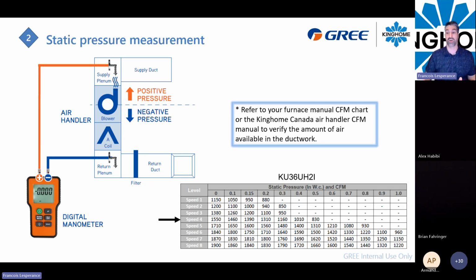If you have more than 400 CFM, the thing is, the condensate water can be blown out of the coil, so you can have some water leak if you are over 400 CFM. Also the performance will be reduced, as you will not have the proper temperature differential because you have too much air. And at a certain point, depending on how you did your ductwork, if you have more than 400 CFM, it will be very noisy. In the house, your static pressure will be very high and it will be very noisy. So make sure you fit around 400, maybe a little bit less.